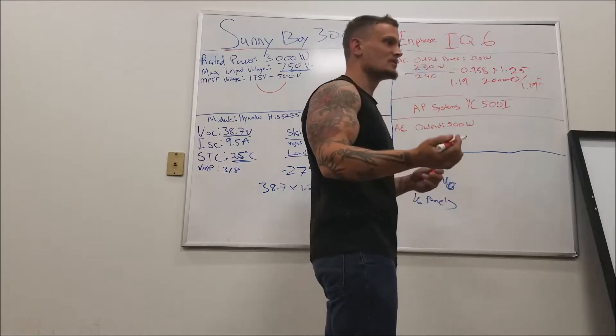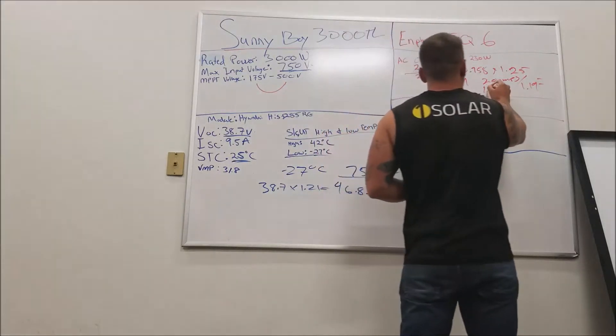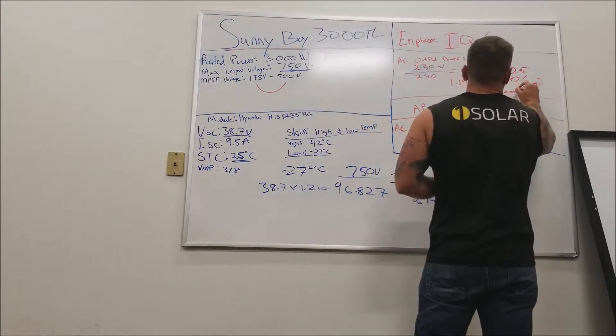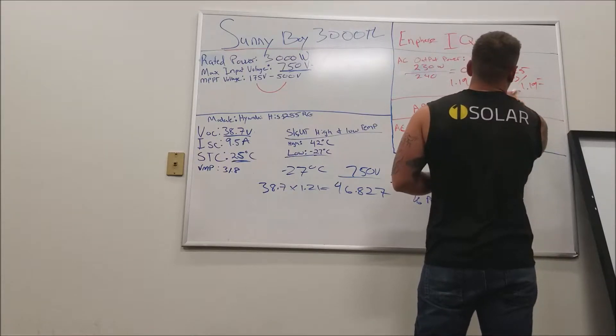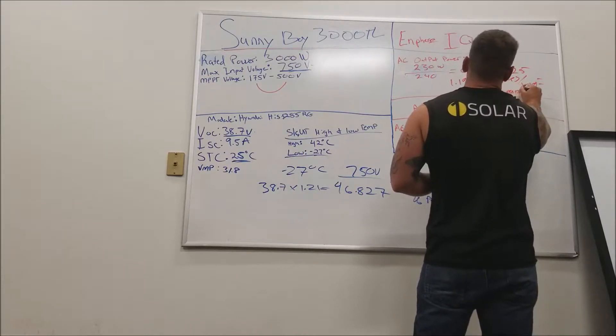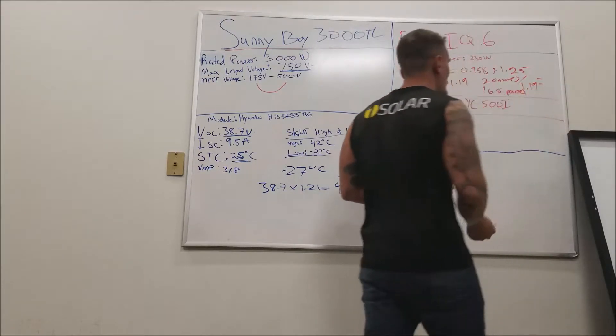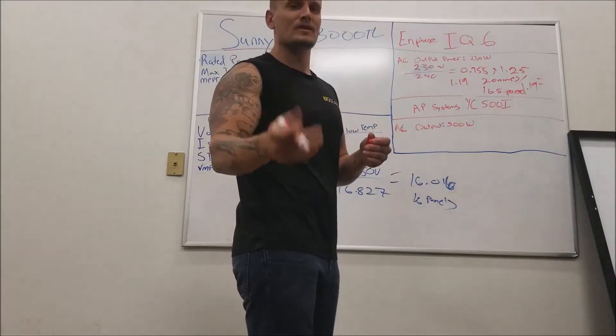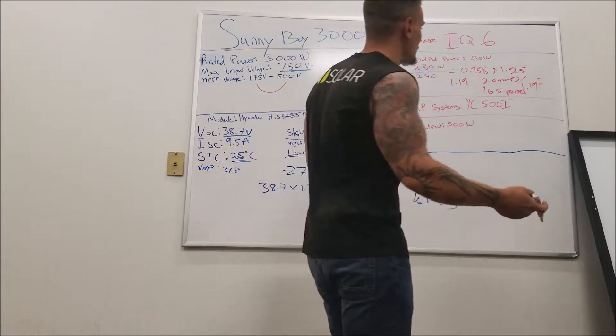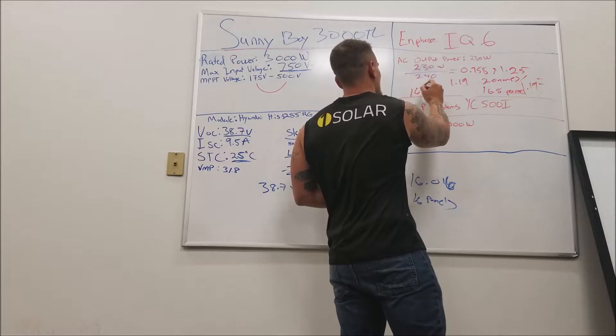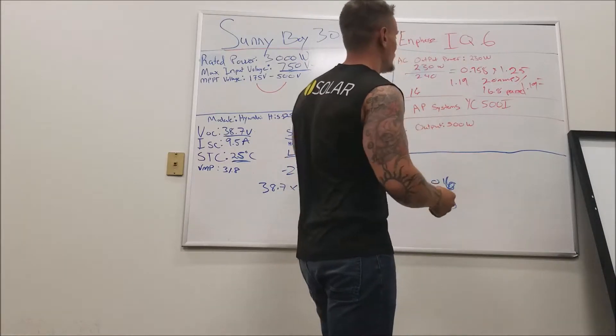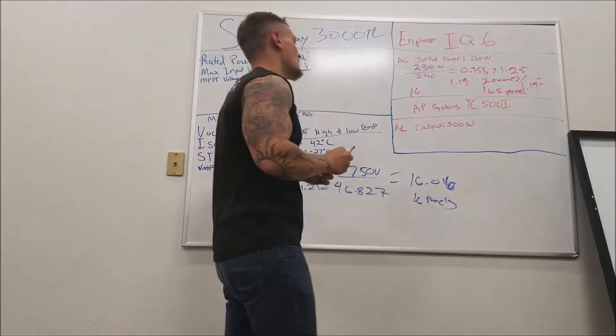That gives us 16.8. You can't put 0.8 of a microinverter on a house, so we're going to take 16 microinverters — 16 panels for that branch circuit.